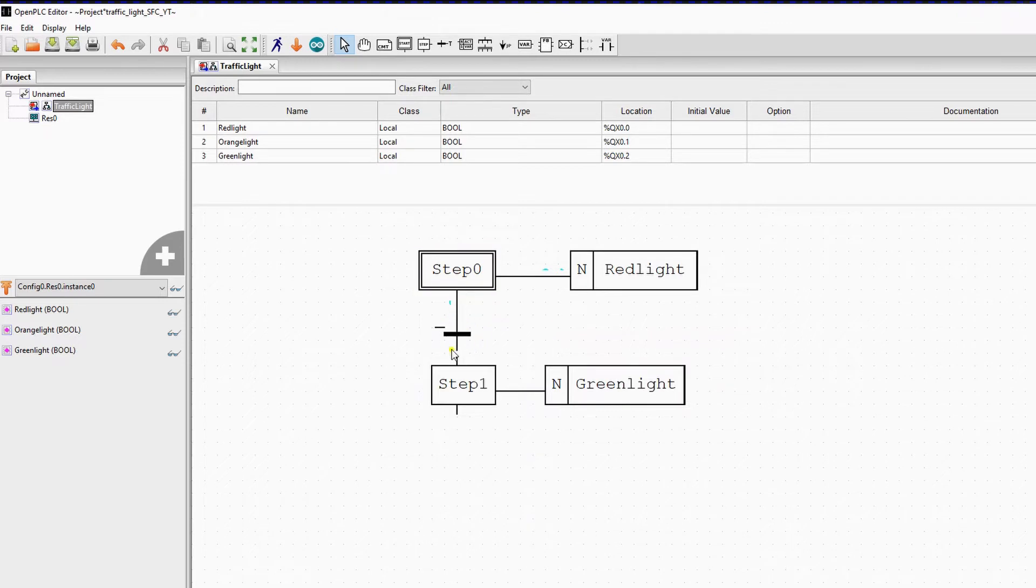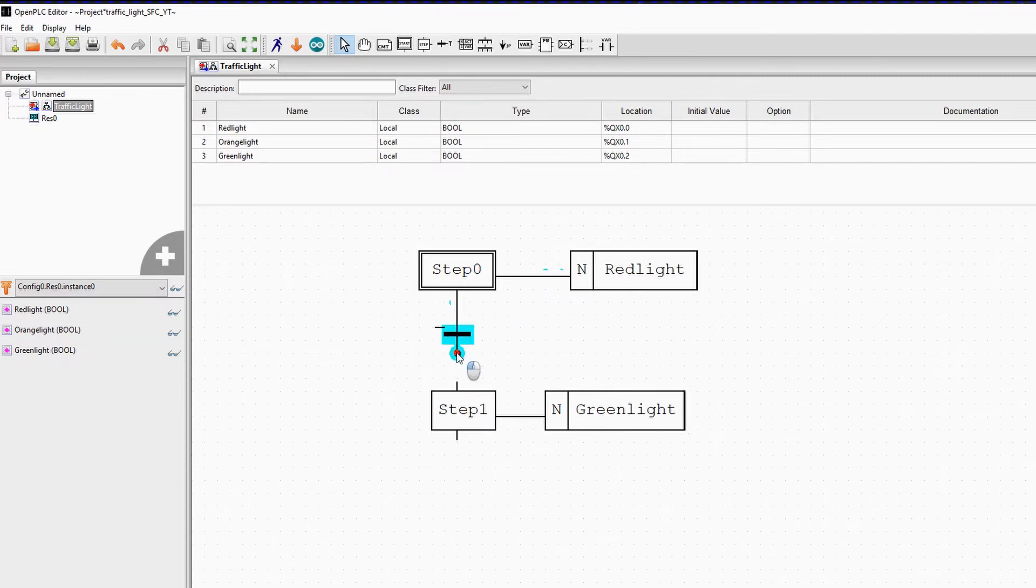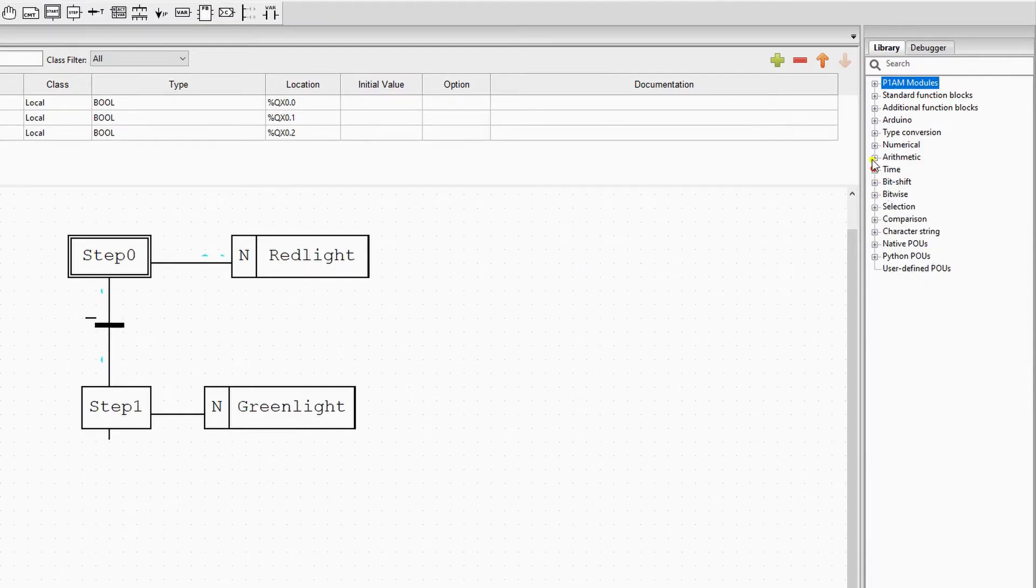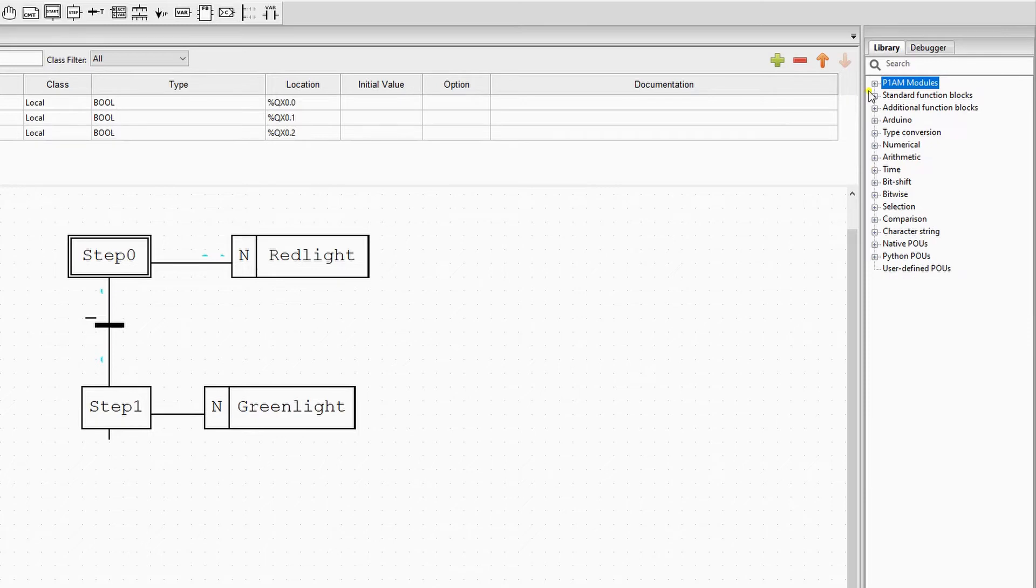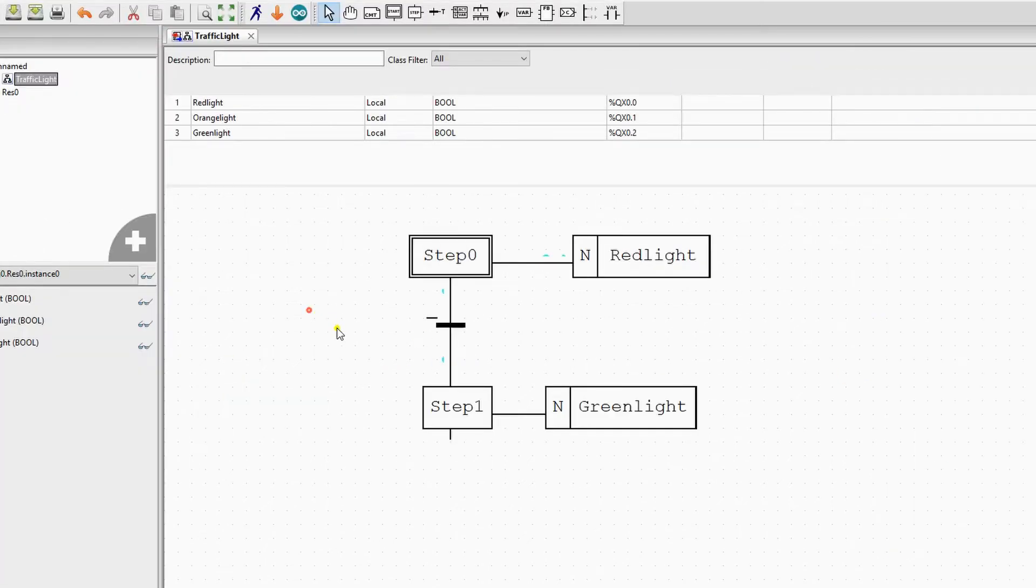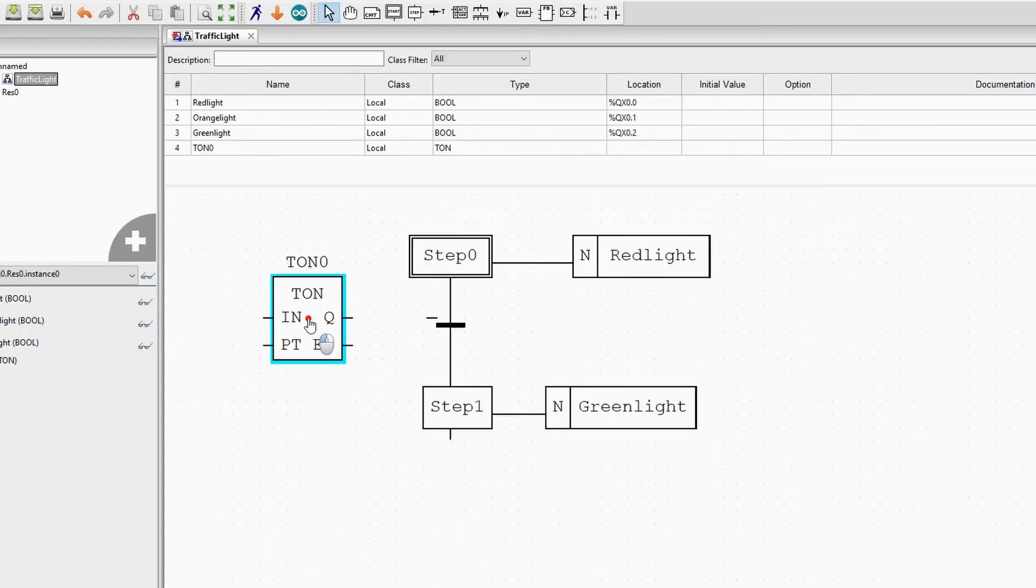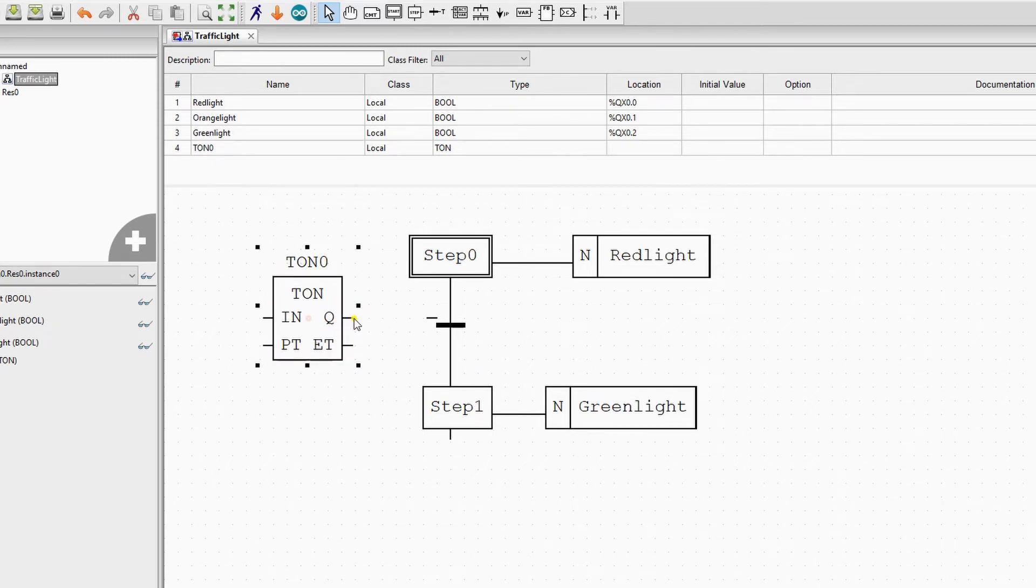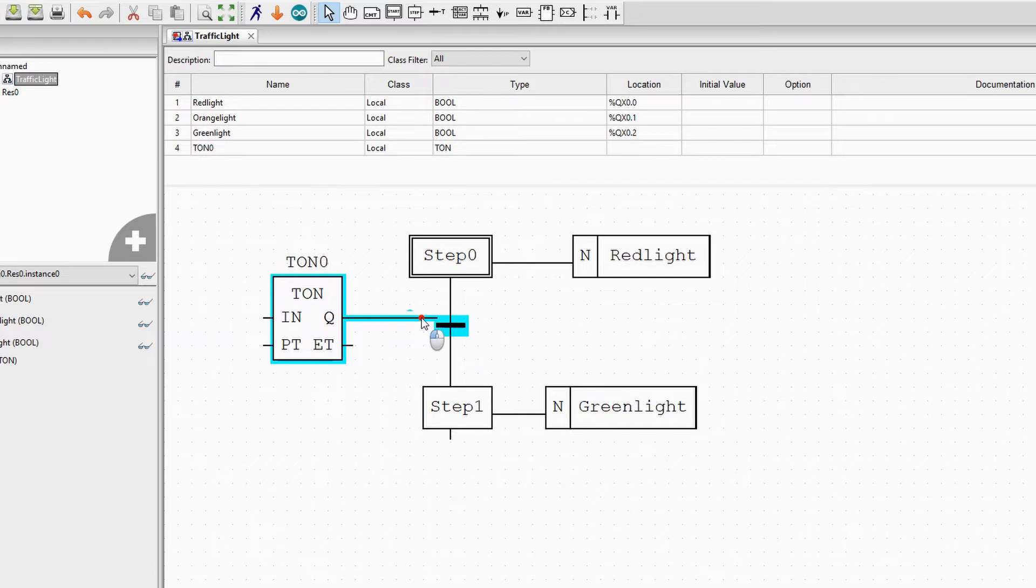Now we'll add some logic. We want to use a timer so that six seconds after the red light is turned on, the green light will turn on. The most visible and intuitive way to do this in my opinion is to use a TON timer in the transition statement. To set the time of the TON statements you add a variable with this statement. To start the timer we could use the red light statements, or even more clean is to create a variable for this specific task.